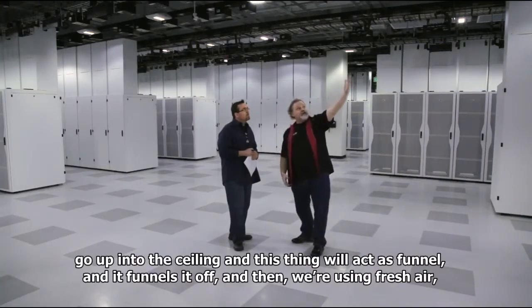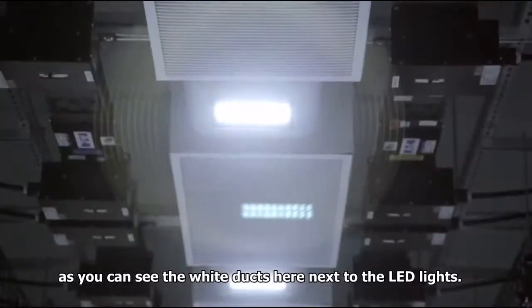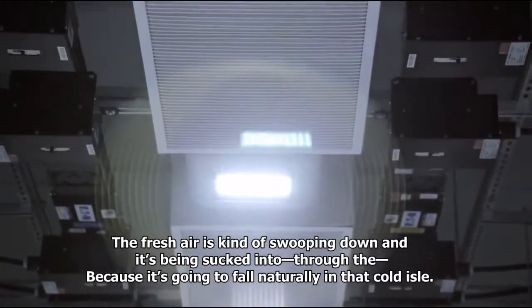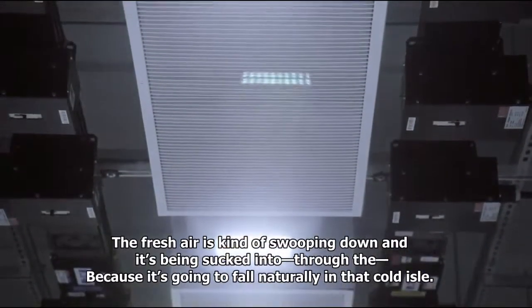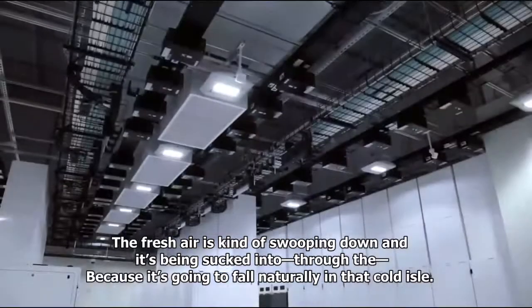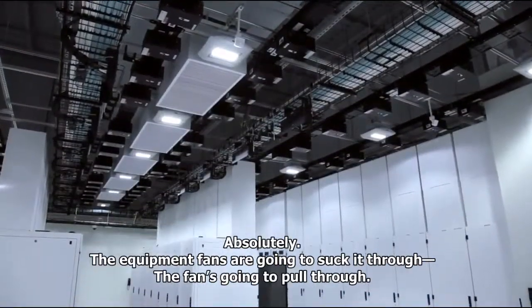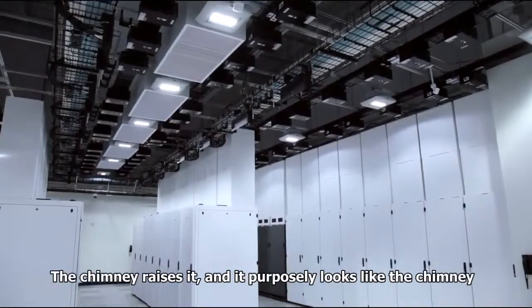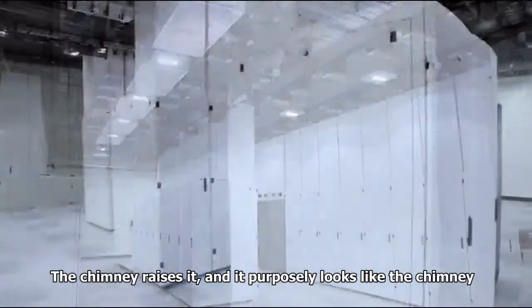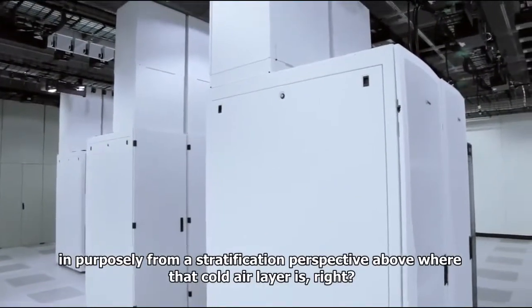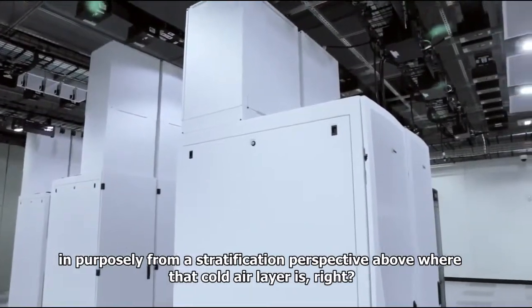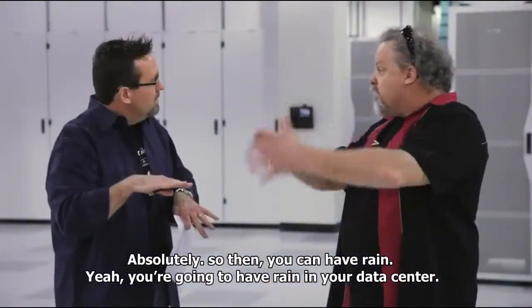And then we're using fresh air -- you can see the white ducts here next to the LED lights. The fresh air swoops down and gets sucked in because it falls naturally into the cold aisle. The equipment fans suck it through, and the chimney raises the hot air. It looks like the chimneys end purposely, from a stratification perspective, above where that cold air layer is -- so the two aren't fighting each other. You don't have rain in your data center.